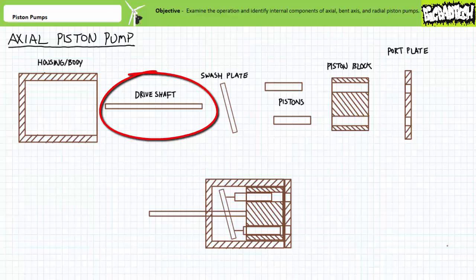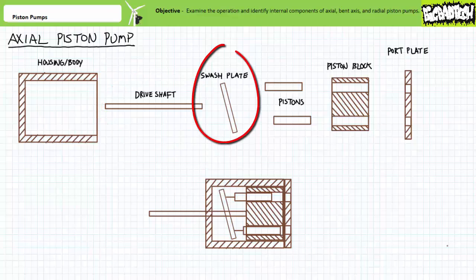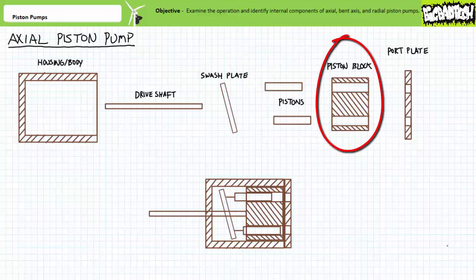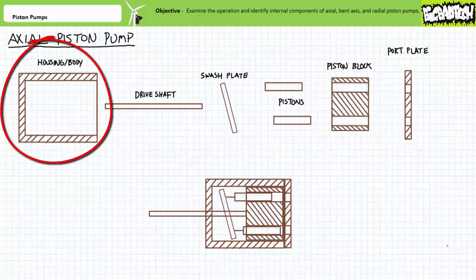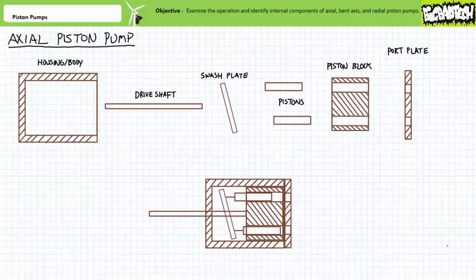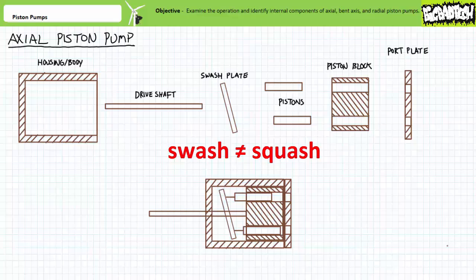An axial piston pump features a drive shaft to which an angled plate called a swash plate is affixed. Pistons are attached to the swash plate and the pistons are housed inside a piston block that is also fixed to the drive shaft. A housing or body encapsulates these parts and a port plate with an inlet and outlet port covers one end. Note: it's pronounced swash plate, not squash plate.